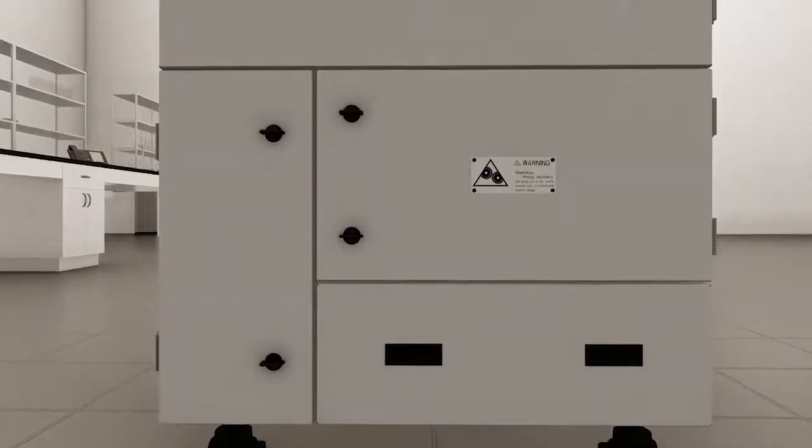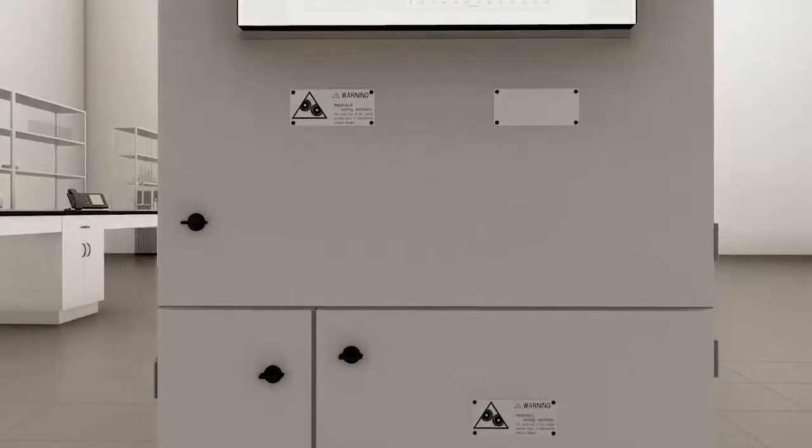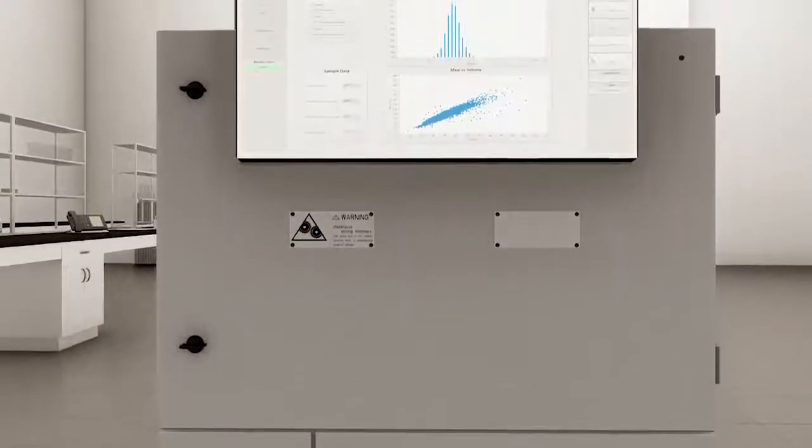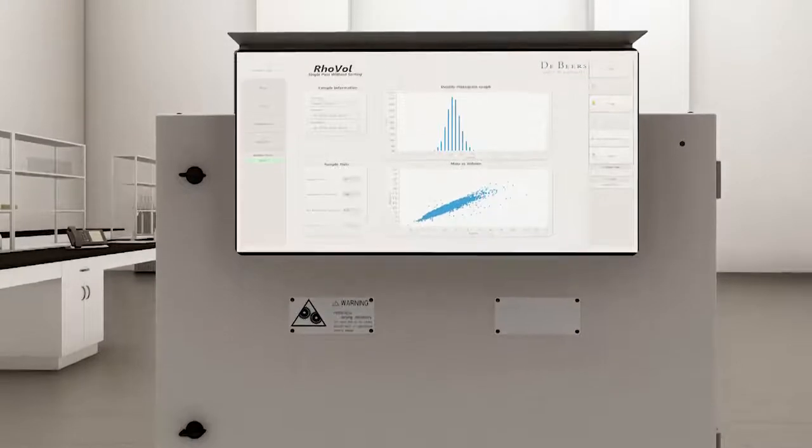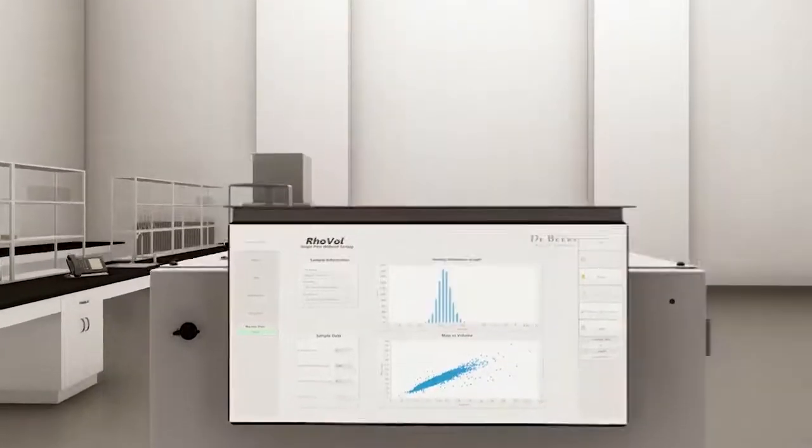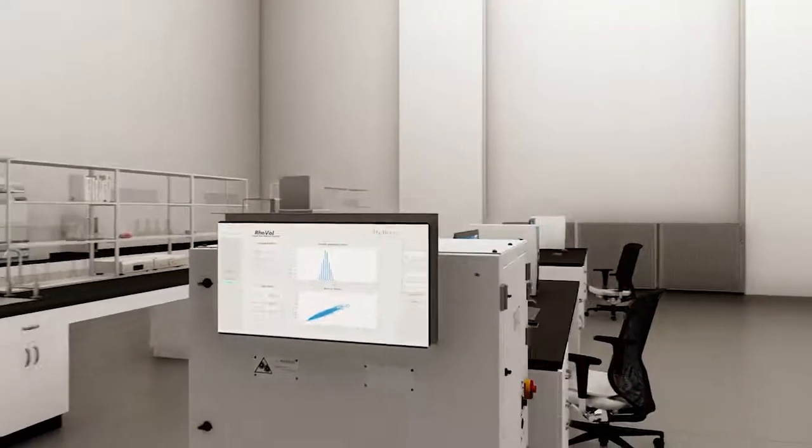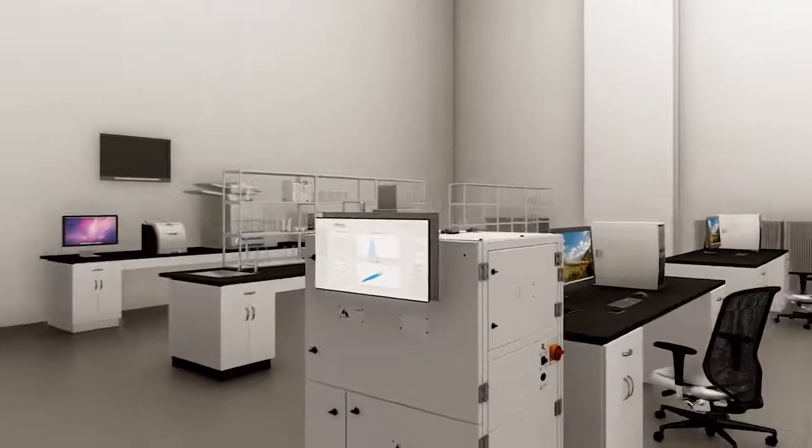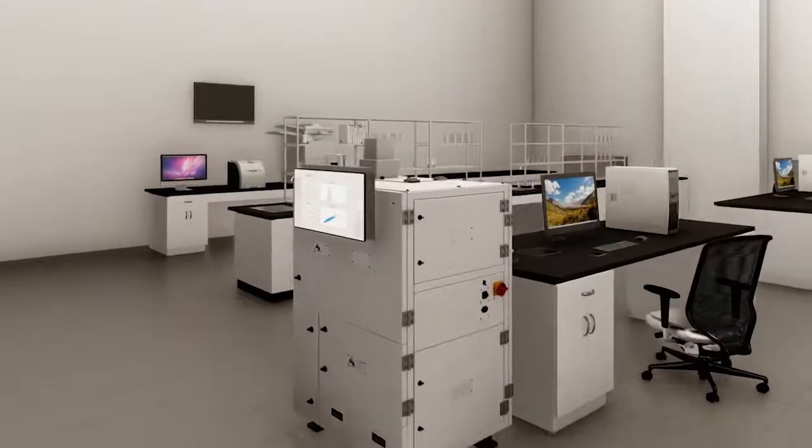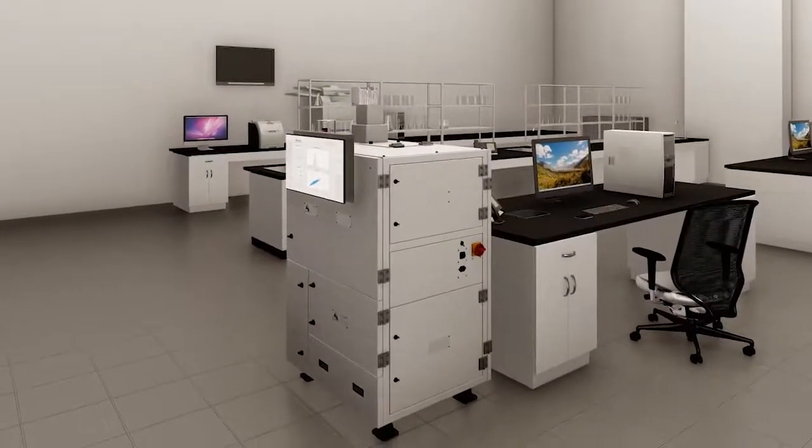The RhoVol technology not only provides users with a fast and accurate density profile of any DMS process, but is also capable of providing a multitude of shape characteristics. It is intended to be used on-site in a laboratory environment and will produce timely and dependable data to the on-site metallurgist to facilitate ore analysis and plant interventions.